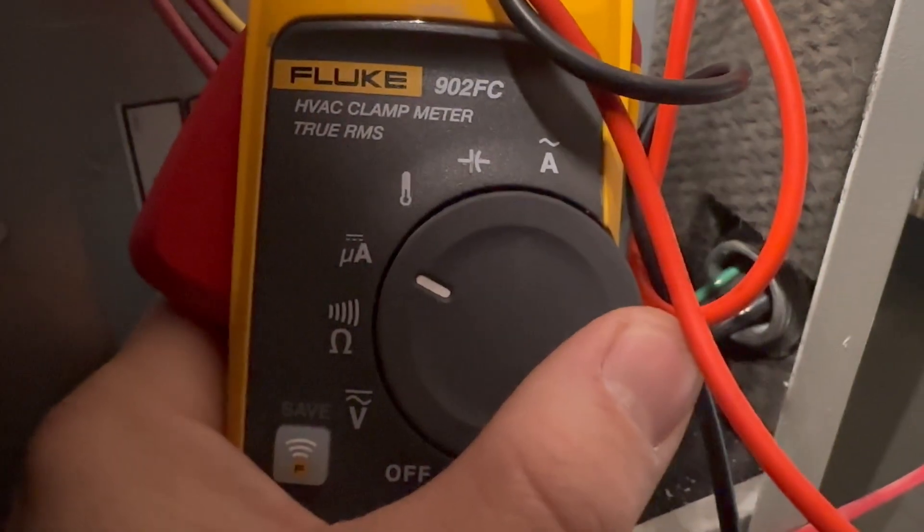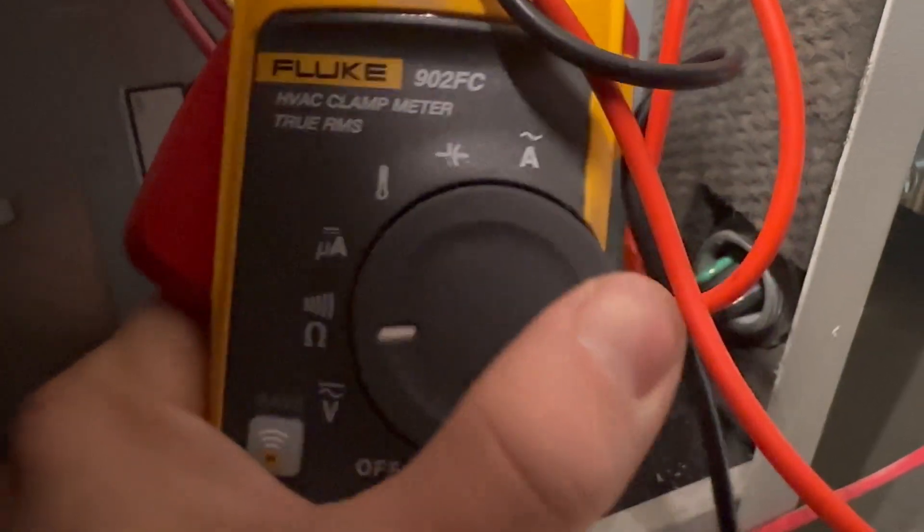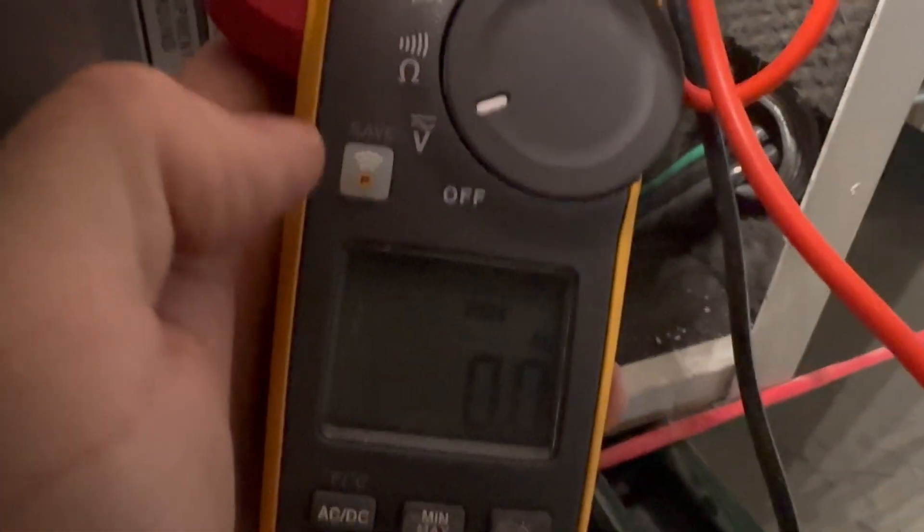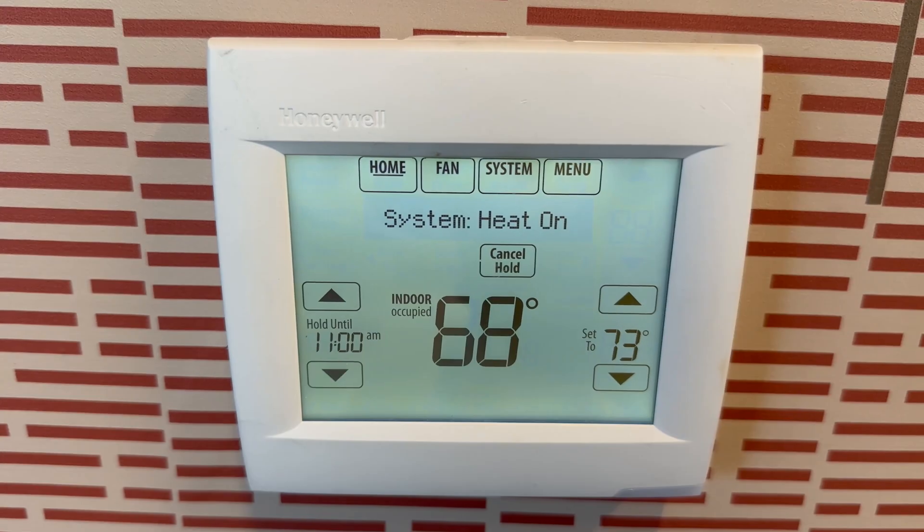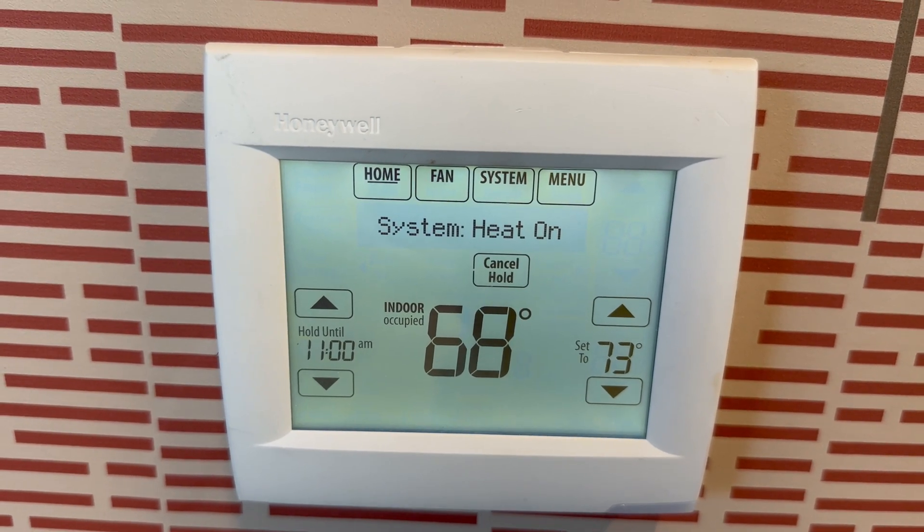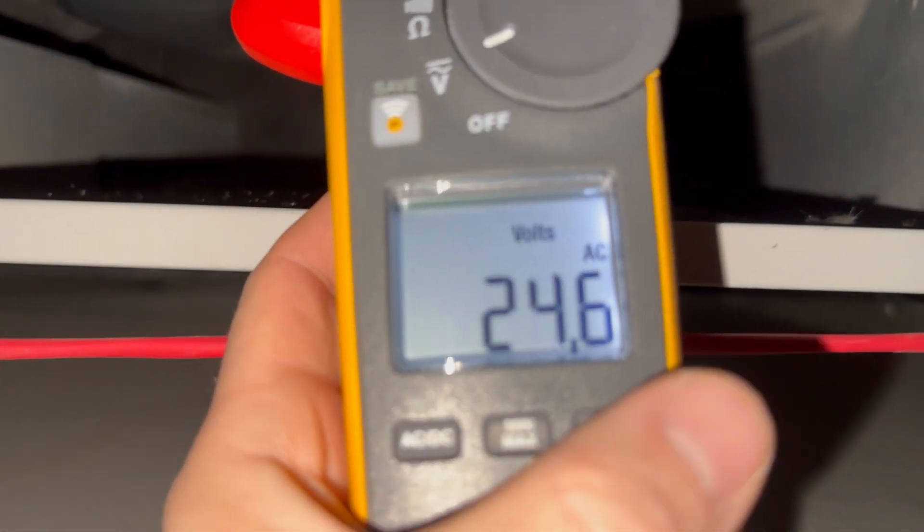Now I'm going to set my multimeter to AC voltage. I would usually just jump out the heat to force it on but I'm going to use the thermostat and we have 24 volts across the heat sequencer coil.